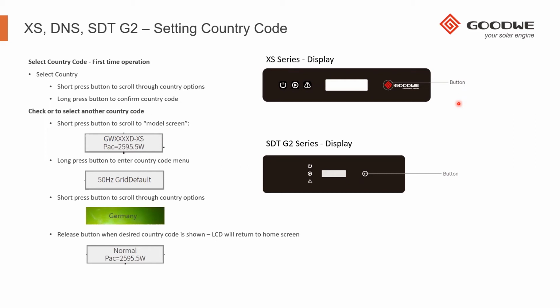If the wrong safety code was selected during commissioning, you can change the country code. Short press the buttons on the inverter until you see the model screen, which shows the actual model number of the inverter and its production date. Once you reach this screen, long press the button again to enter the country code menu, then short press the buttons to select the grid code. For example, you might see Germany on the screen. Once you see the correct country code, release the button and the menu will go back to the main menu, showing the power output of the inverter as normal. It's very simple to set the country code.